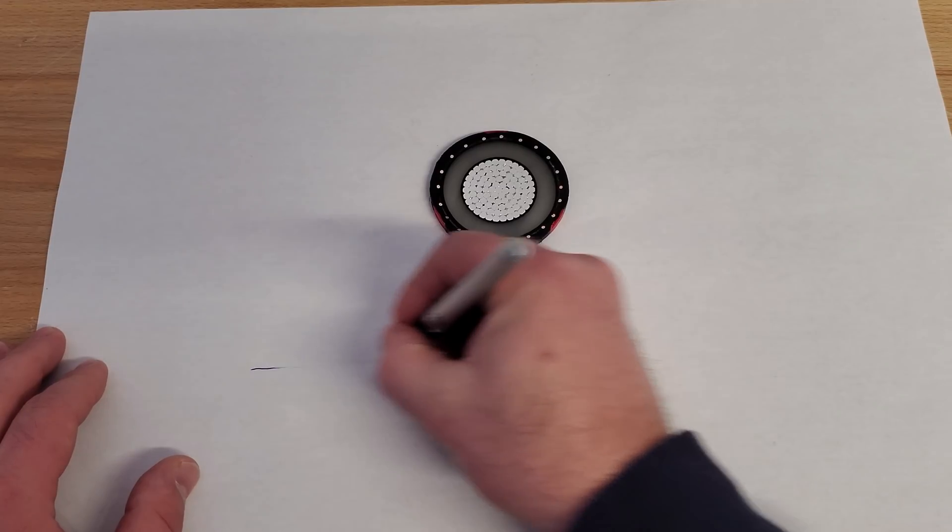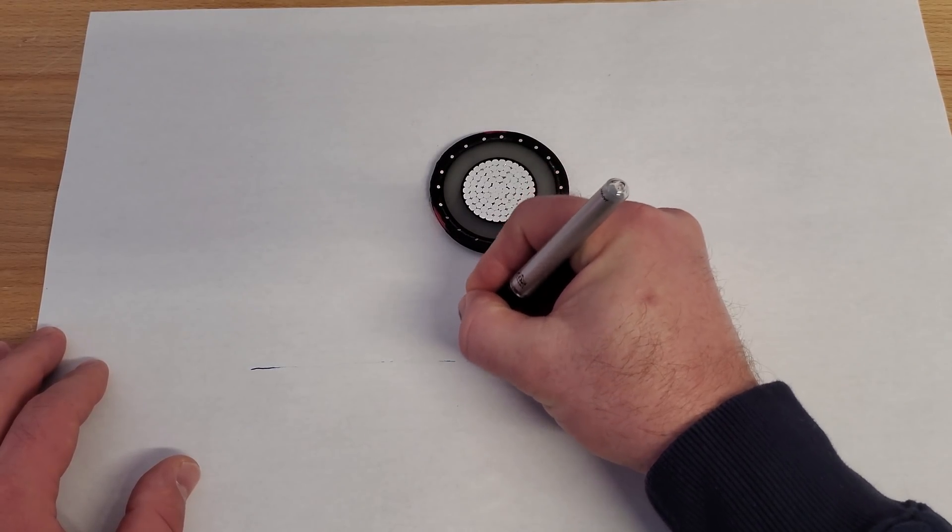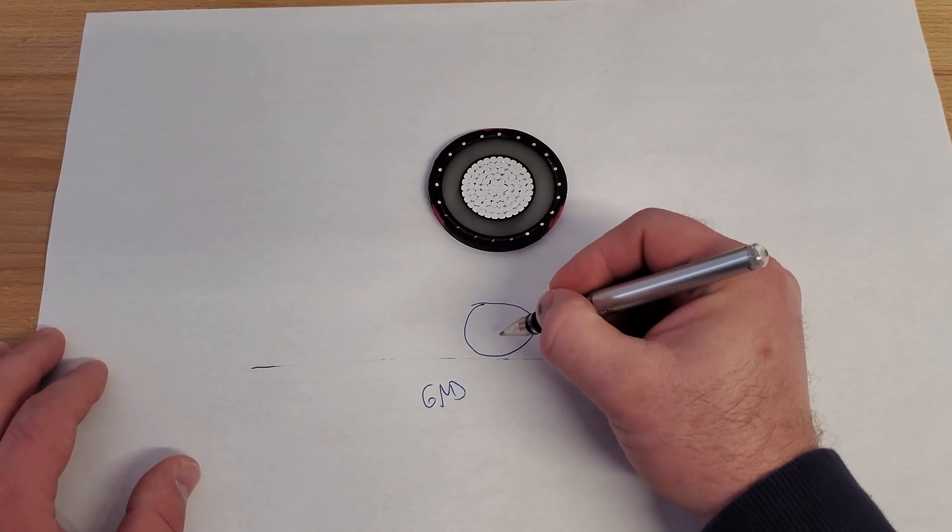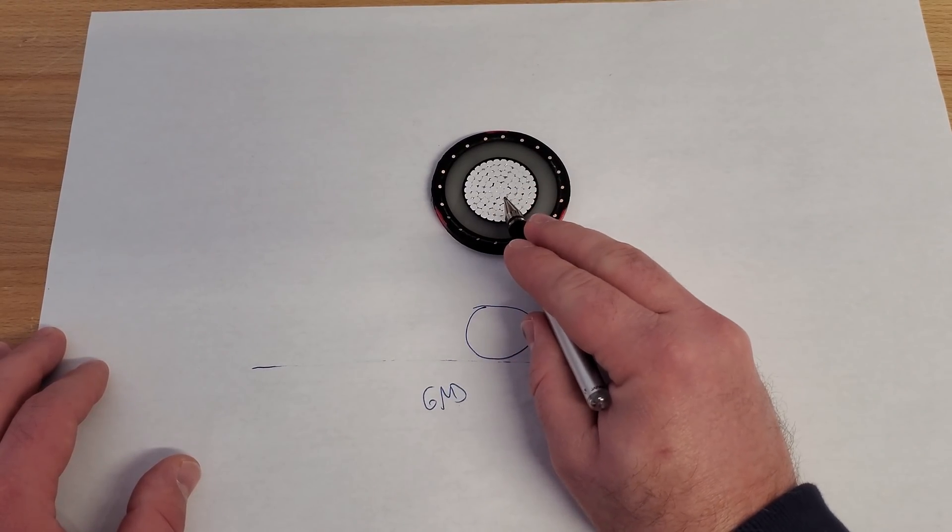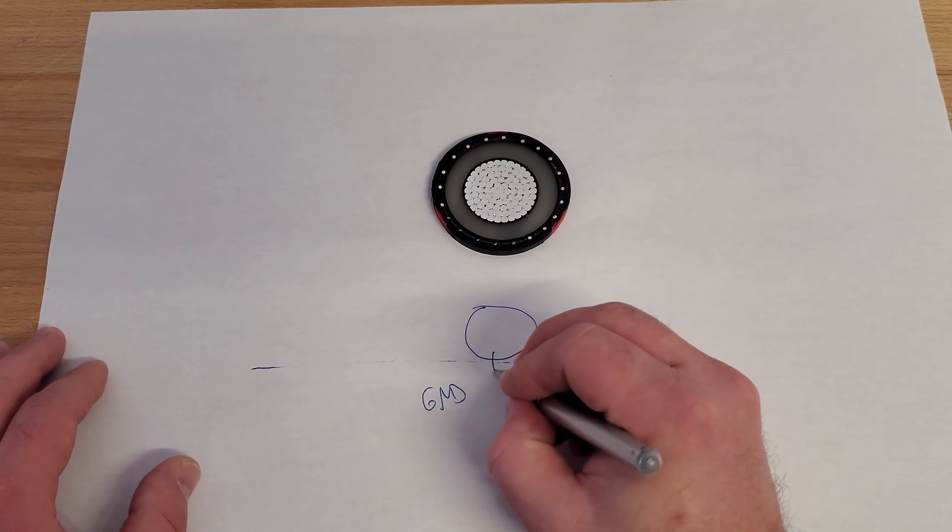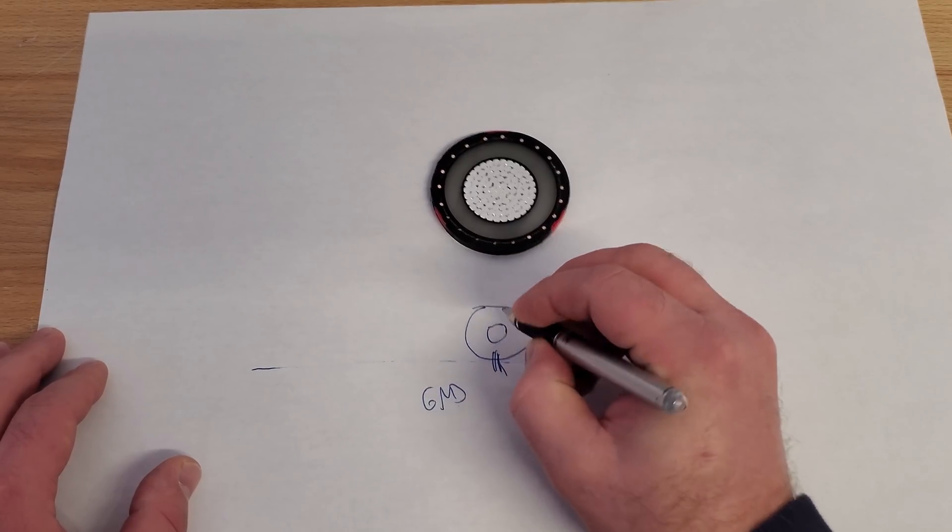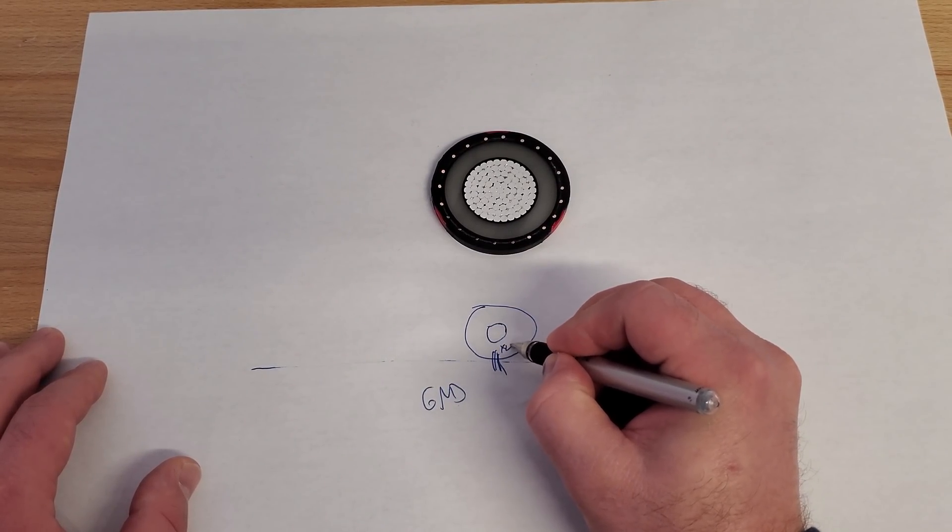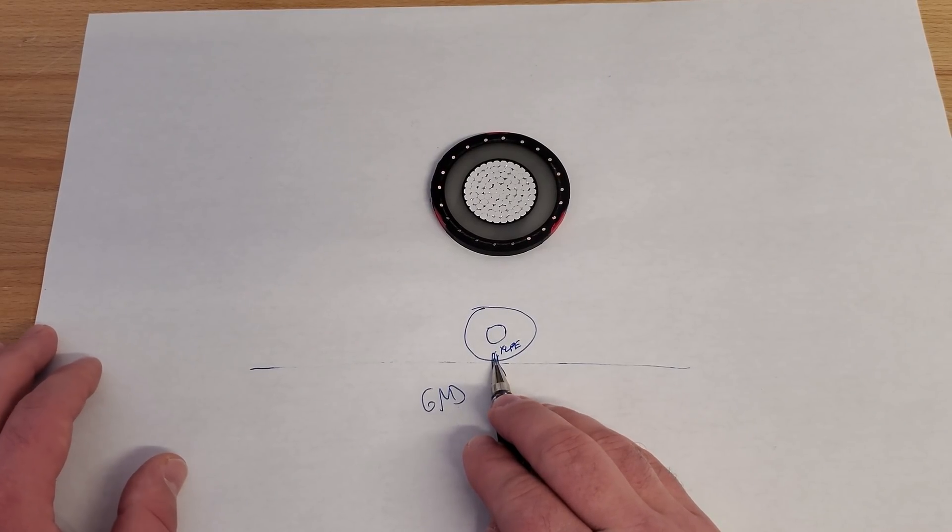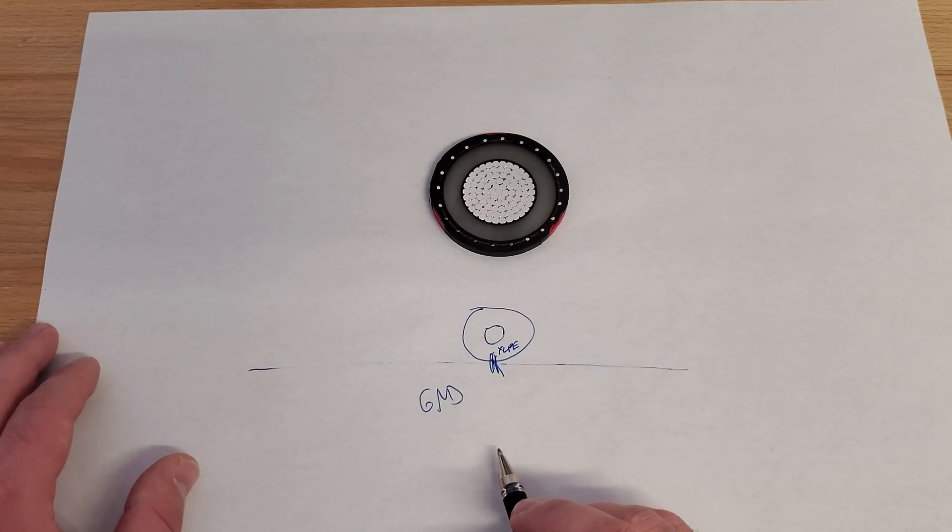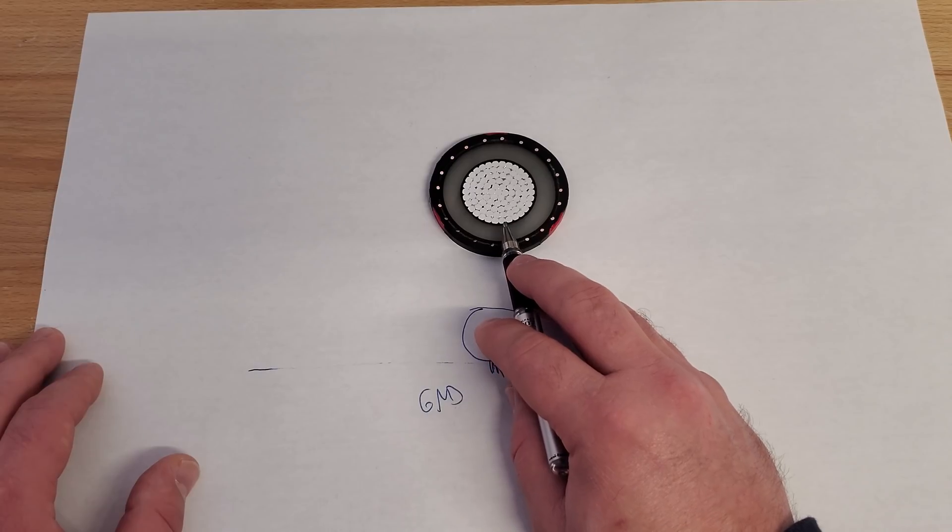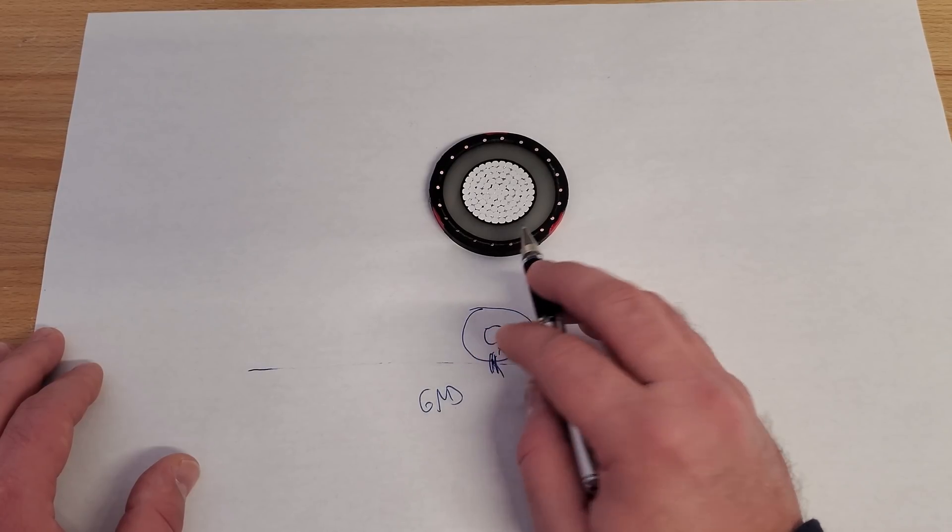It's to prolong the life. So how is that? If you have a cable laying on the ground, right here, this is the ground. You're going to have bleed from the flux to ground. And if you do not have any of these layers, it's going to bleed right here. This is your conductor. This is your insulation. XLPE. It's all going to bleed through this part of the insulation and it's going to break that insulation down over time. And that's what reduces the life of your cable.